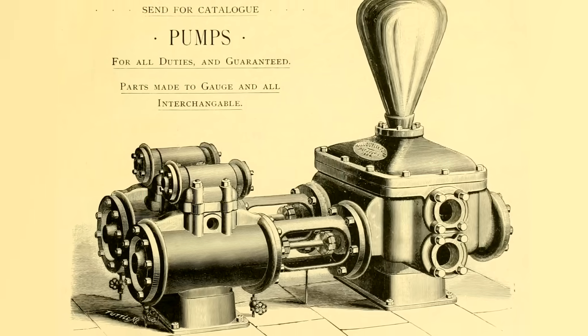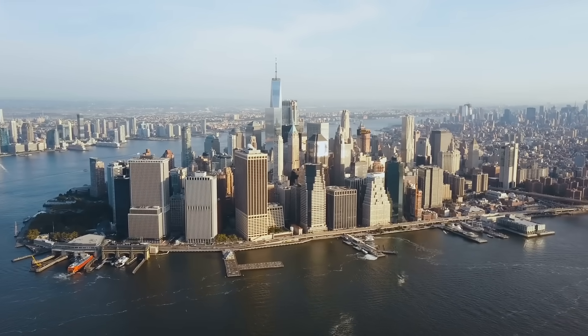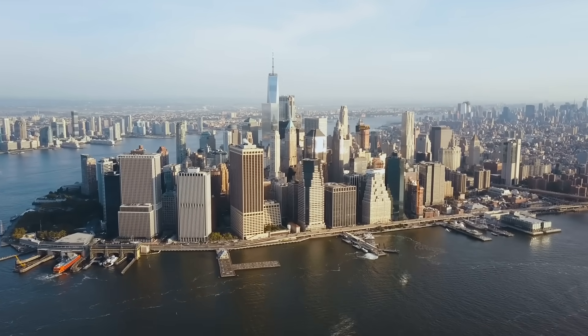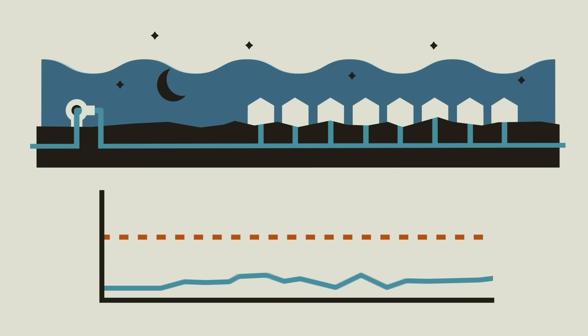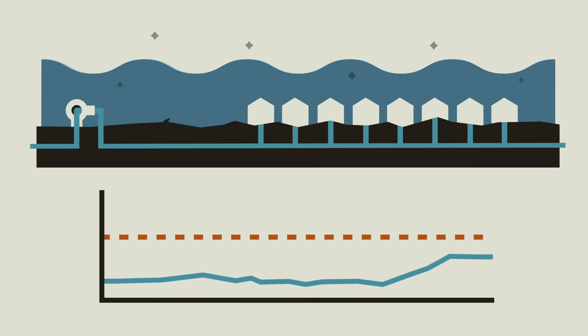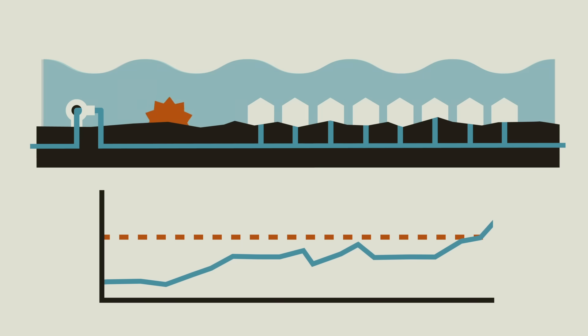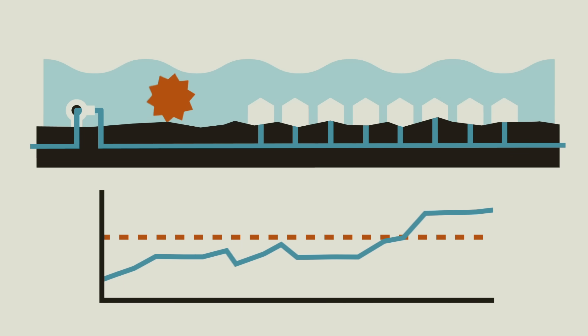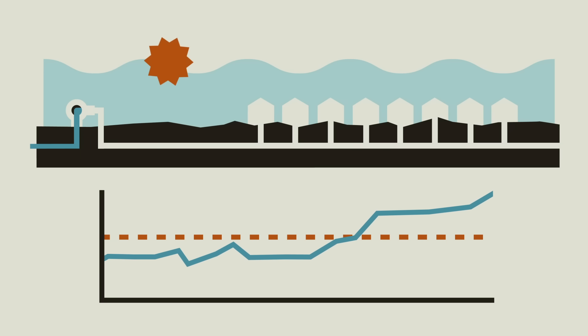So if you're tasked with choosing the size of pump for your public water system, what do you do? Maybe you measure the amount of water a city uses in a given day and select a pump that can match that flow rate. It's midnight in your city and most customers are asleep — water demands are minimal and your pump has no trouble meeting them. But around 5 am, automated sprinkler systems start kicking in. Around 6 am, people start waking up, taking showers, brushing their teeth, cooking breakfast — all things that require water. It doesn't take long before demand exceeds the pump's capacity, because it was only sized for the average.